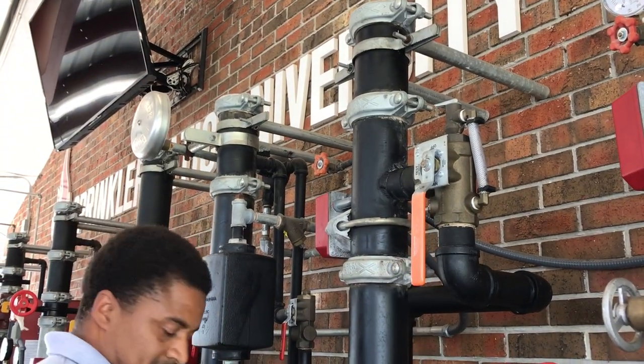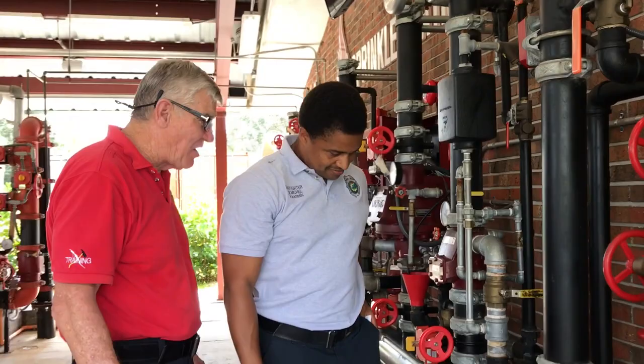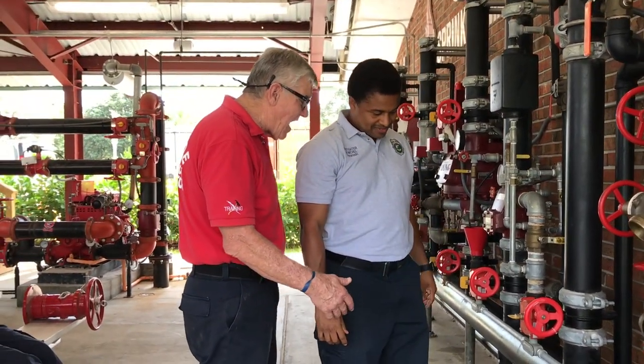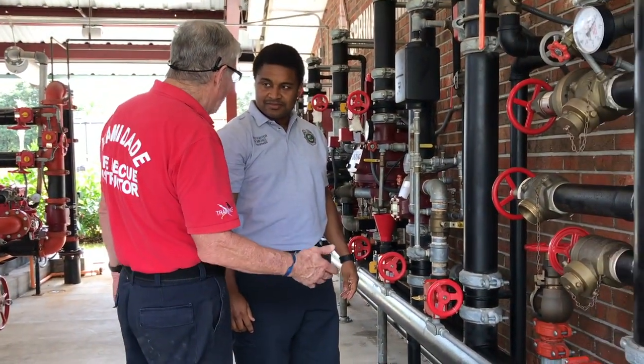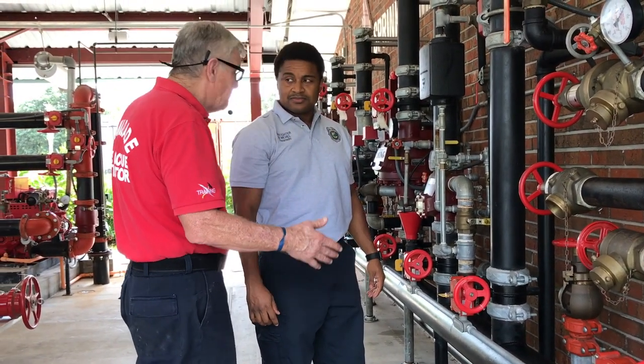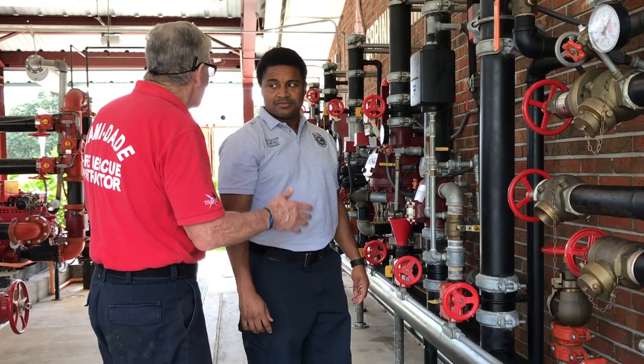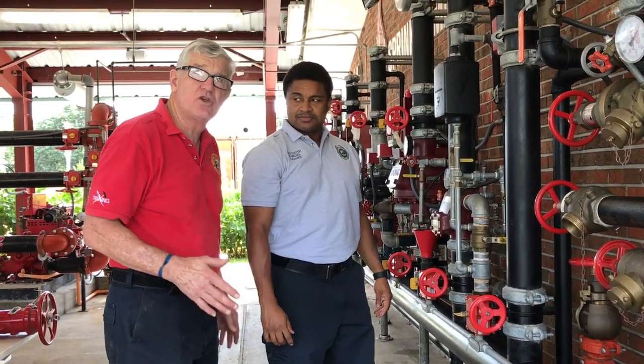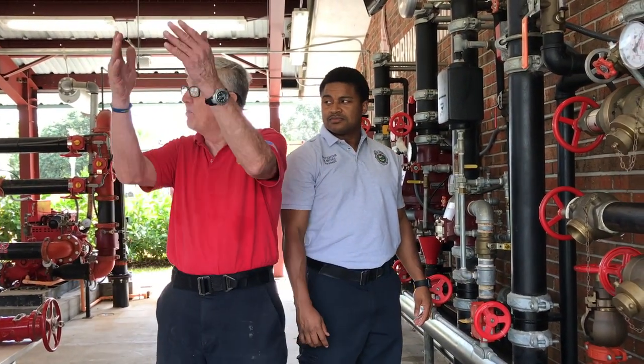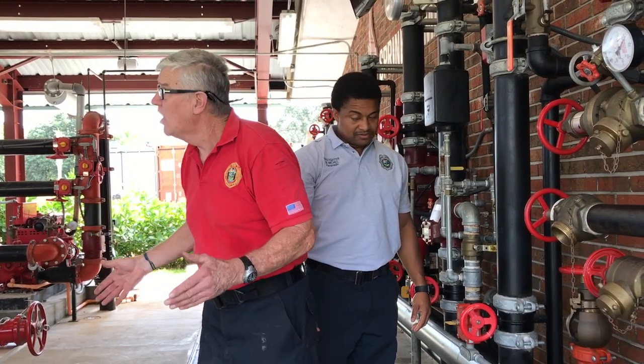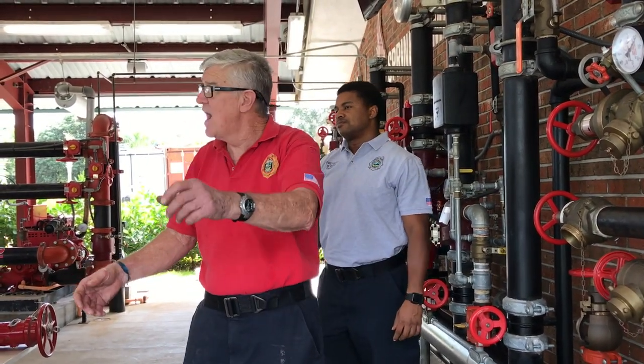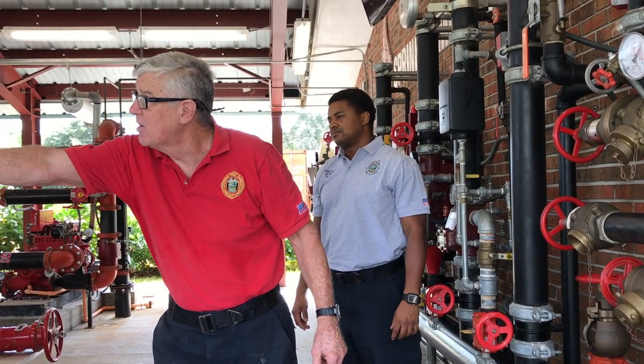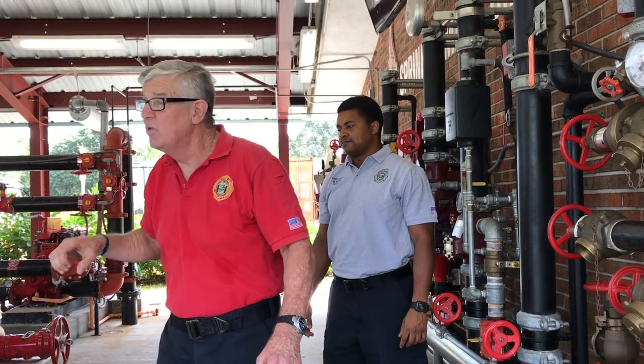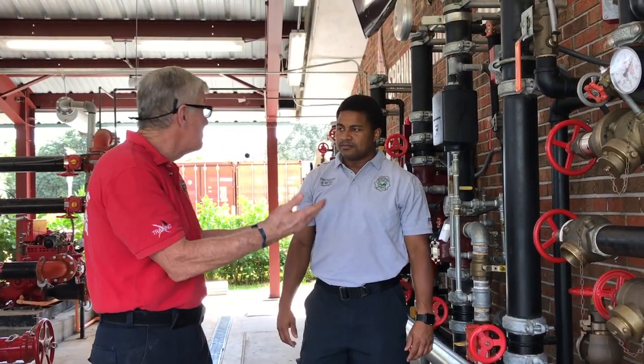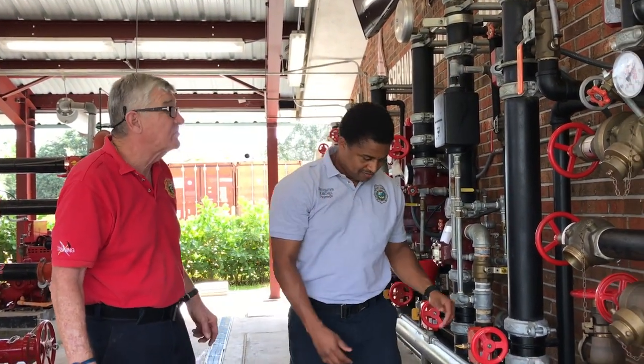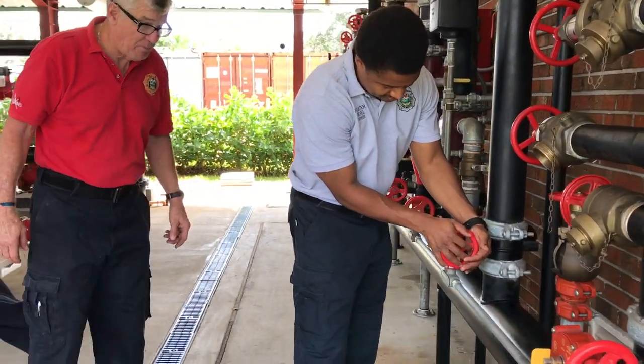Mark, we're gonna do this on purpose. It may or may not turn on the fire pump, but I'm gonna ask you to open it fairly fast. In reality, if the building had a fire pump, we would shut that fire pump down because we would never use the fire pump to fill open sprinkler piping any more than would we pressurize a hose line or pressurize our pump at 300 PSI and yank a valve open. We would shut off the fire pump and allow the jockey pump to work. But go ahead and open it up. Let's see if we'll set the fire pump off.